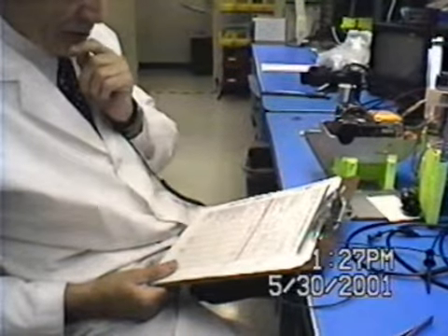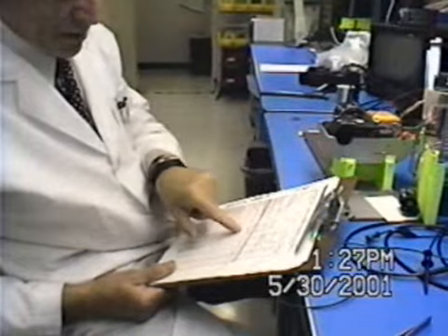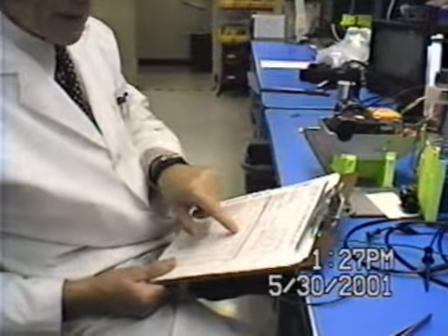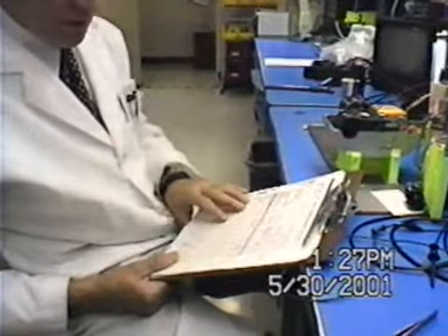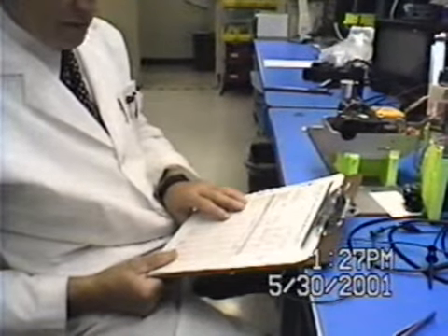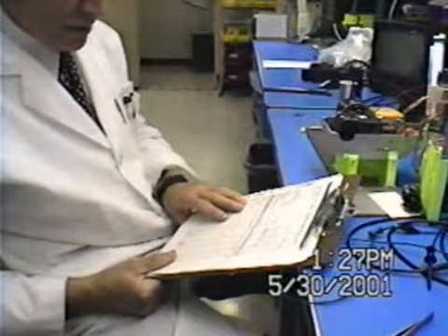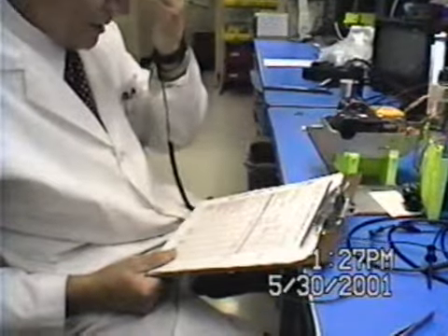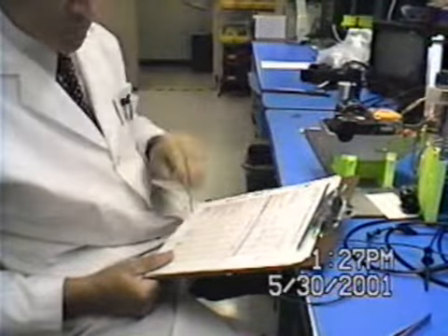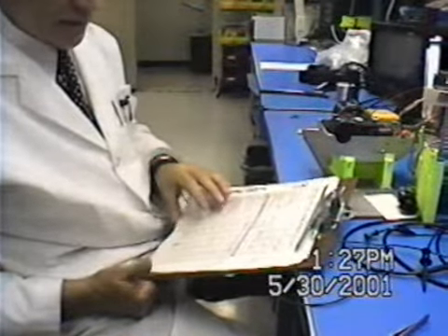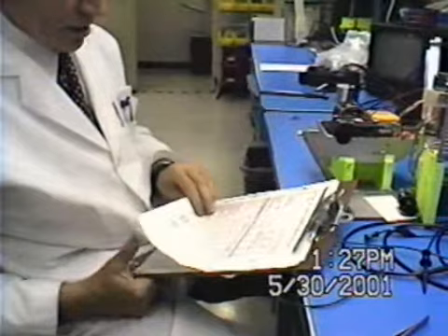However, previously we had adjusted the emissivity, but now that we have changed the feedback resistor for the DC path so drastically by a factor of 3, the gain for the AC signal also had been reduced. We had to recalibrate the emissivity channel.